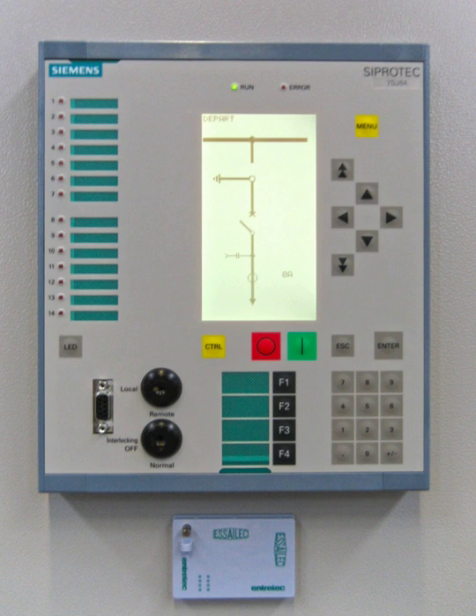Topic: backup. The objective of protection is to remove only the affected portion of plant and nothing else. A circuit breaker or protection relay may fail to operate. In important systems, a failure of primary protection will usually result in the operation of backup protection. Remote backup protection will generally remove both the affected and unaffected items of plant to clear the fault. Local backup protection will remove the affected items of the plant to clear the fault.